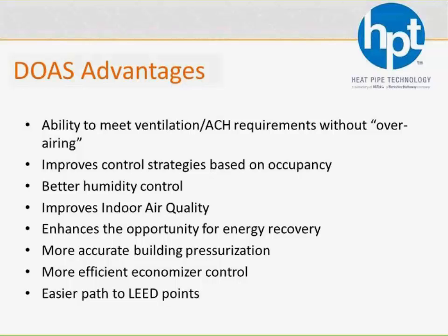You also get some nice occupancy control out of it, whether we're talking occupied versus unoccupied, or a demand control ventilation system where CO2 sensors are estimating the amount of people out in the space. It gives you a lot better control from an occupancy standpoint to reduce the amount of ventilation air going to the space. You obviously get better humidity control. Instead of one mixed air coil doing everything, you've got one coil solely committed to drying out the outside air, which is where the bulk of that humidity is coming from. And that's going to lead to better indoor air quality. Less threat of moisture being in the space means less threat of mold and mildew being out in the space, and that's obviously a good thing.